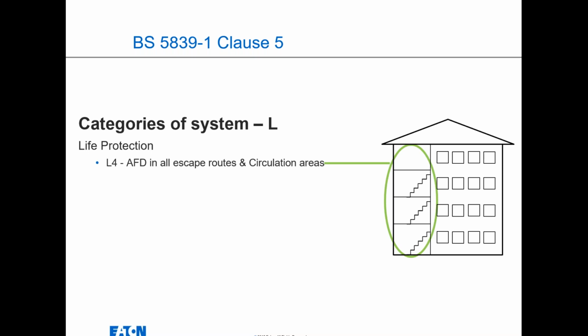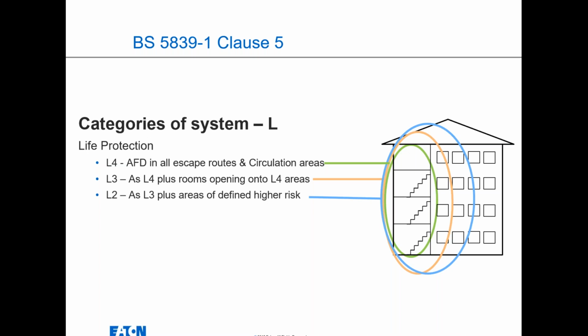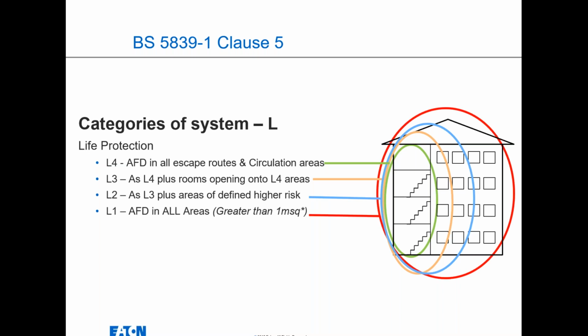The different levels, you go through L4, which is just alarms in, detection within the escape routes and the circulation areas, such as stairwells. And L3, it's the same as L4, but then you add on some rooms that open onto the escape routes. L2 is the same as an L3, but it's a risk assessment driven design, and your risk assessment then determines if you've got any other rooms outside of that defined in the standard that you might need detection in, and that could be an insurance driven thing. So you can't really do an L2 design unless you've got a risk assessment, and an L1 is just detection in all areas, and obviously then all your sounders and call points, etc., etc.